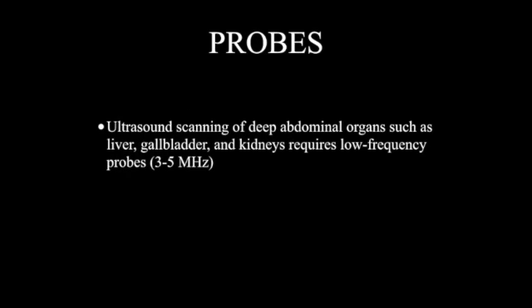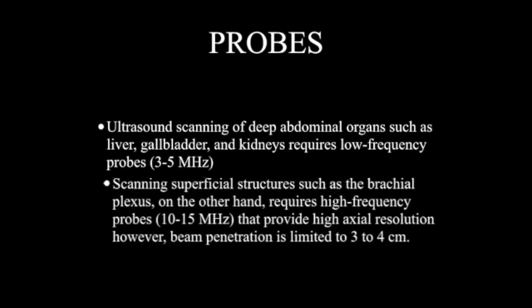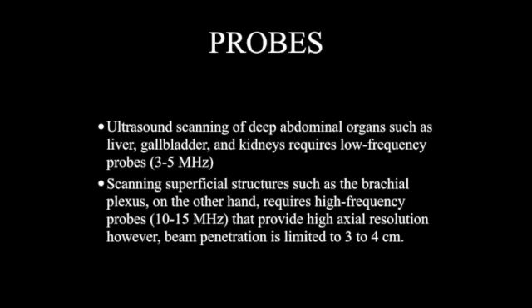When it comes to probes, there are many different types. Low-frequency probes are typically in the range of 3 to 5 megahertz and are typically useful for scanning deeper organs such as the kidney, gallbladder, and liver. Scanning superficial structures, such as nerves of the brachial plexus, may require a higher-frequency probe in the range of 10 to 15 megahertz.